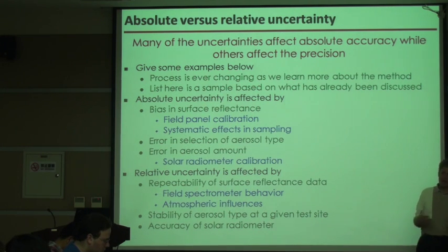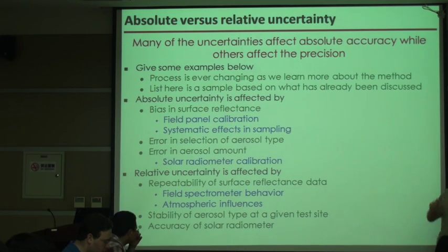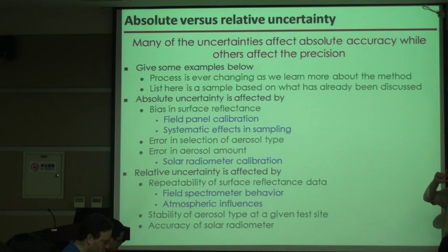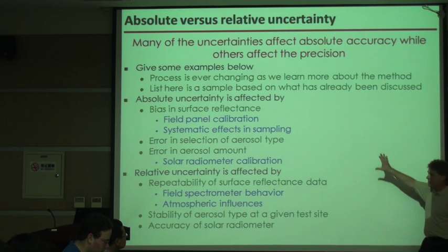If I were to measure that panel reflectance 95 times, the true reflectance I will never measure. I do not know what the true reflectance is, but my actual measured reflectance, plus or minus 2%, will encompass that true reflectance. And it could always be that same difference. I could always be off by positive 1.8%. That's allowed.